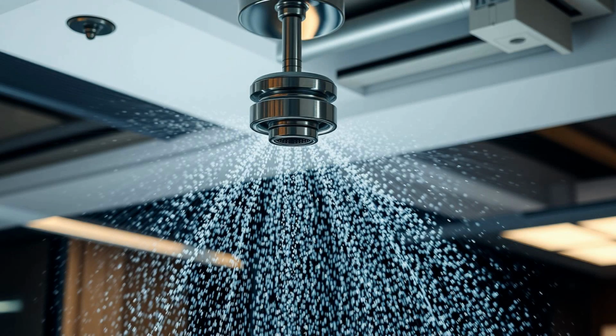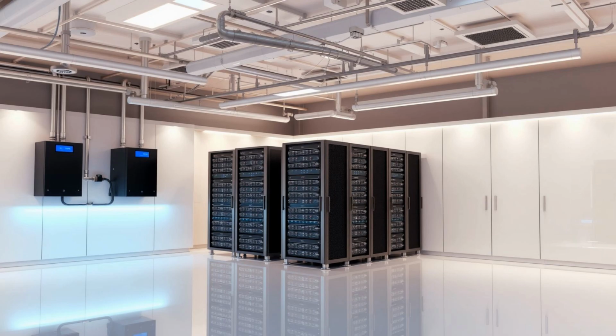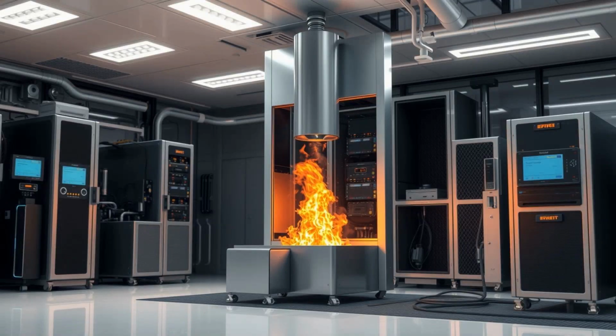Sprinkler systems, arguably the most recognized form of active protection, release water upon detecting a predefined heat level, effectively controlling or extinguishing the fire. In specialized environments where water could cause more harm, such as data centers or museums, clean agent suppression systems like FM200 or inert gases are used. These systems suffocate the fire without damaging sensitive equipment. Fire extinguishers, though manual, remain vital. Available in multiple classes: A for combustibles, B for flammable liquids, C for electrical fires, D for metals, and K for cooking oils, they allow trained personnel to intervene before the fire grows.